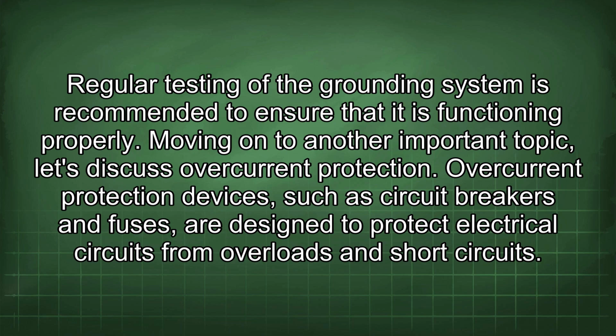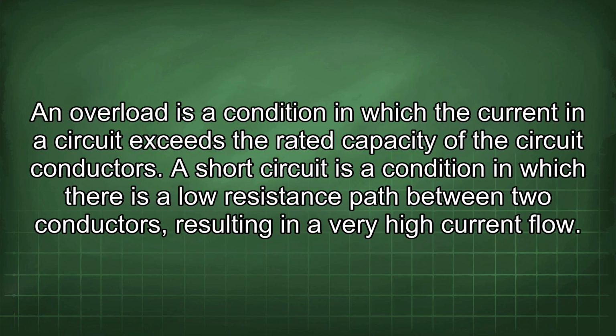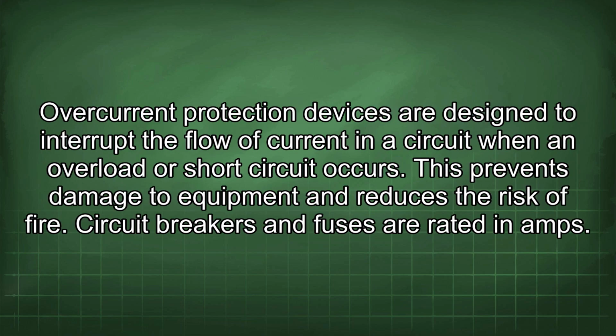such as circuit breakers and fuses, are designed to protect electrical circuits from overloads and short circuits. An overload is a condition in which the current in a circuit exceeds the rated capacity of the circuit conductors. A short circuit is a condition in which there is a low resistance path between two conductors, resulting in a very high current flow. Overcurrent protection devices are designed to interrupt the flow of current in a circuit when an overload or short circuit occurs. This prevents damage to equipment and reduces the risk of fire.